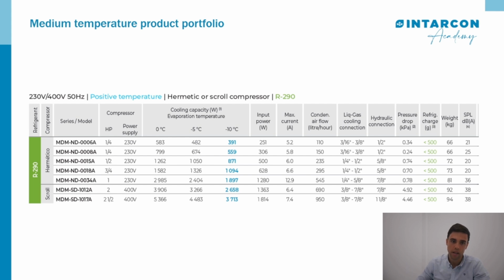Let's see now the portfolio products on medium temperature. For this equipment we will have a reciprocating compressor or a scroll compressor, depending on the chassis. Chassis 0 has a reciprocating compressor, and chassis 1 has a scroll compressor. We are going to have a horsepower range between 1/4 and 2 1/2 horsepower.